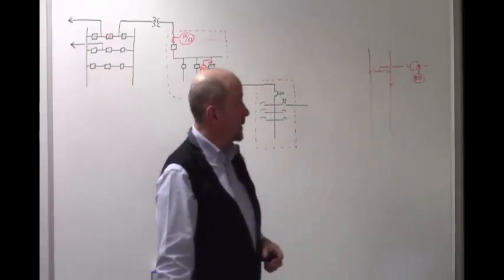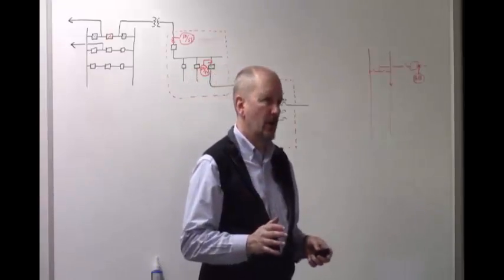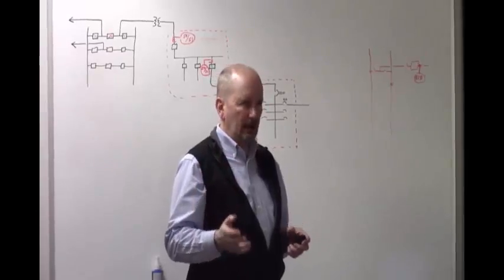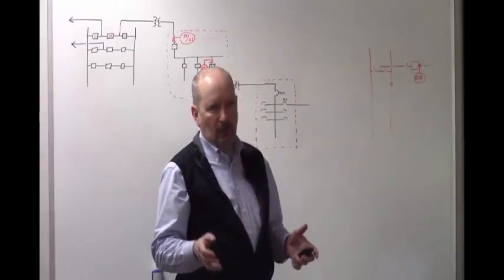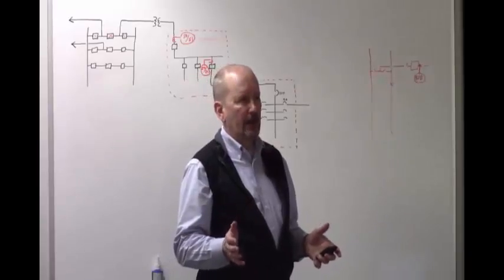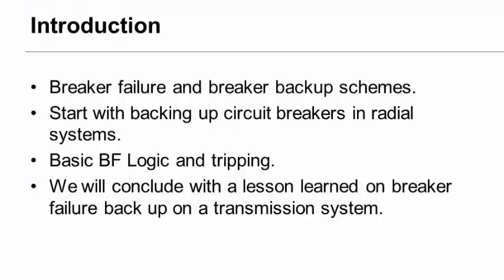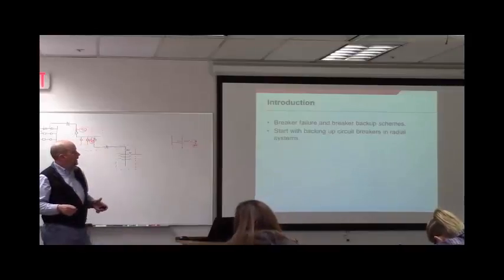Today we're going to talk about breaker failure relaying and the general concept of backing up breakers, so that if a breaker does not operate, you still clear the fault. An uncleared fault on the system, regardless of voltage, is completely unacceptable and will generally lead to a cascading failure and outage of the entire system. It's really critical that within a very short amount of time you clear faults — if a breaker doesn't operate, that's a very serious situation.